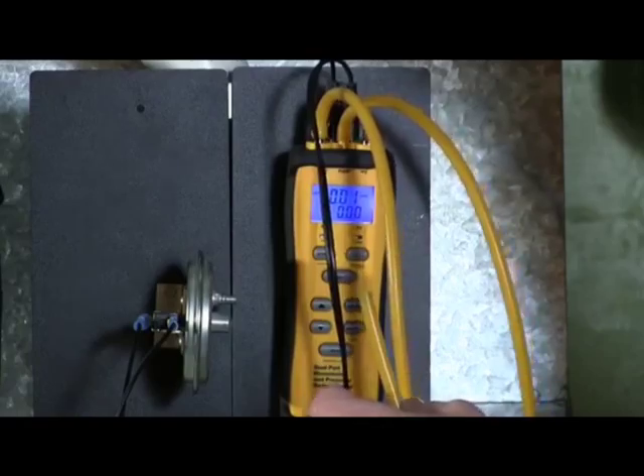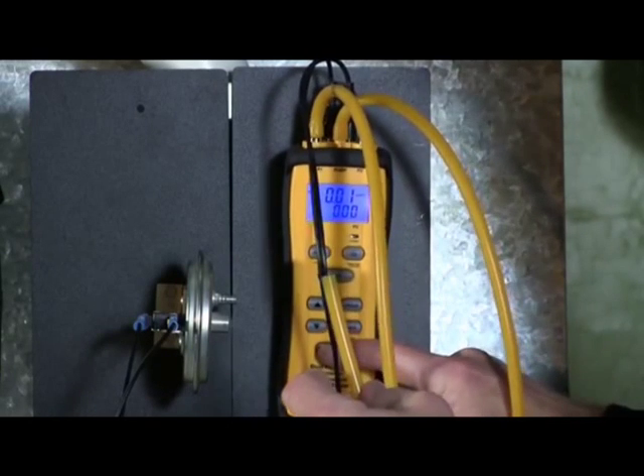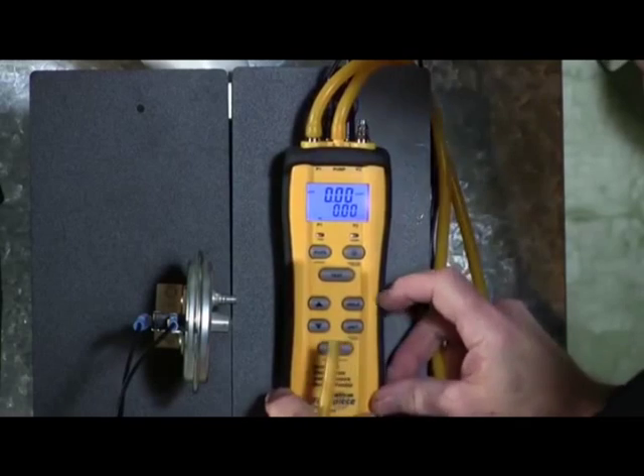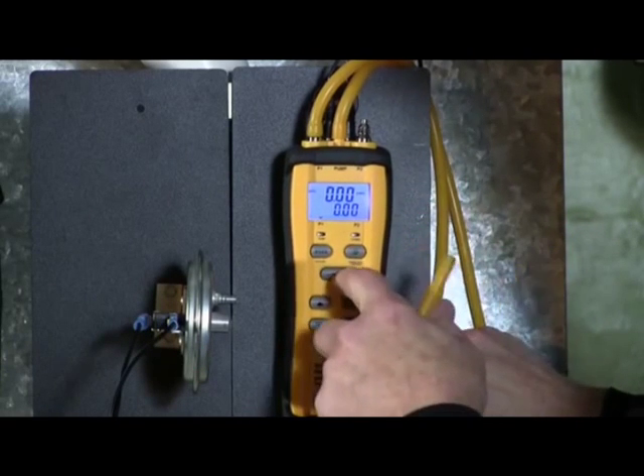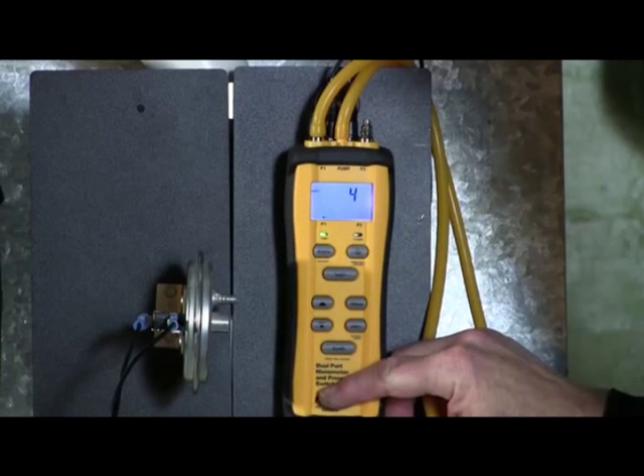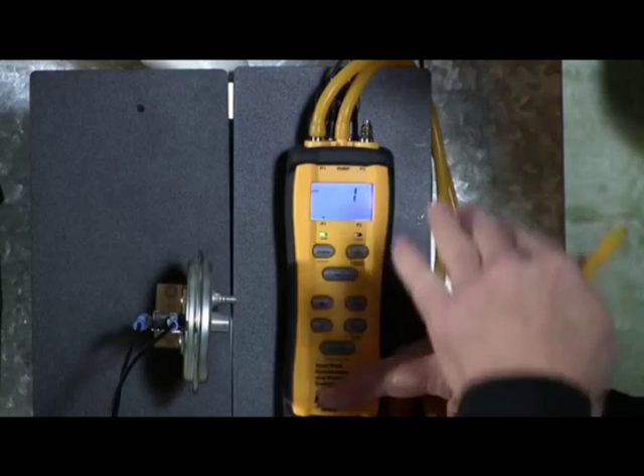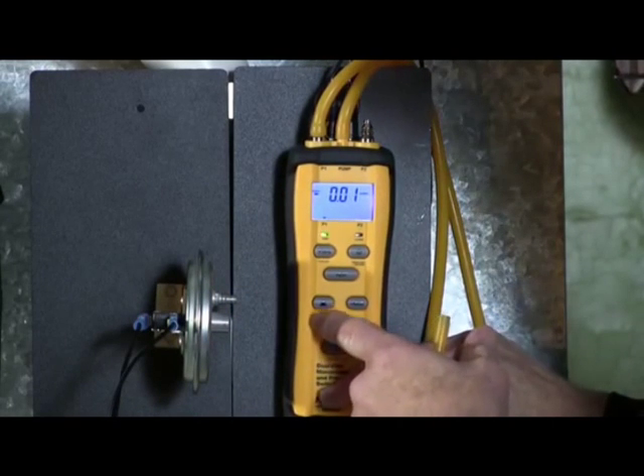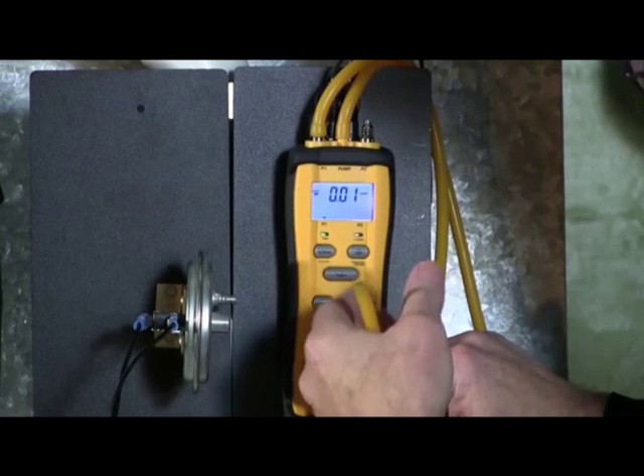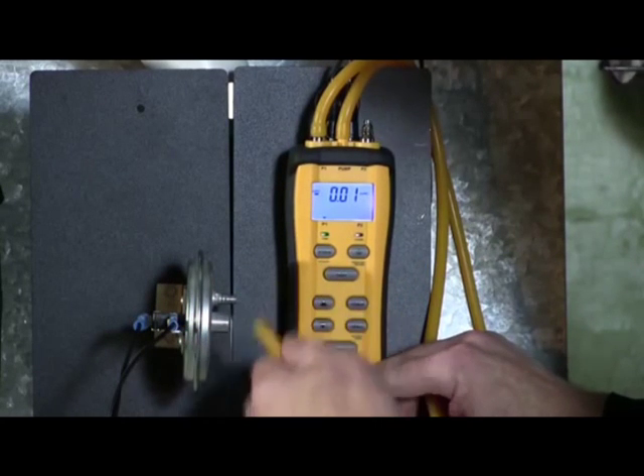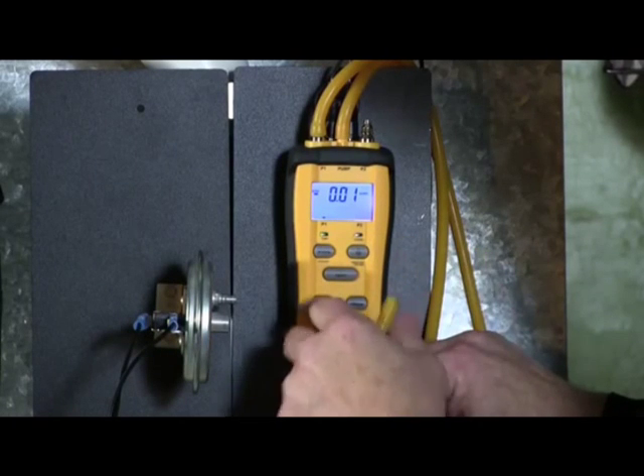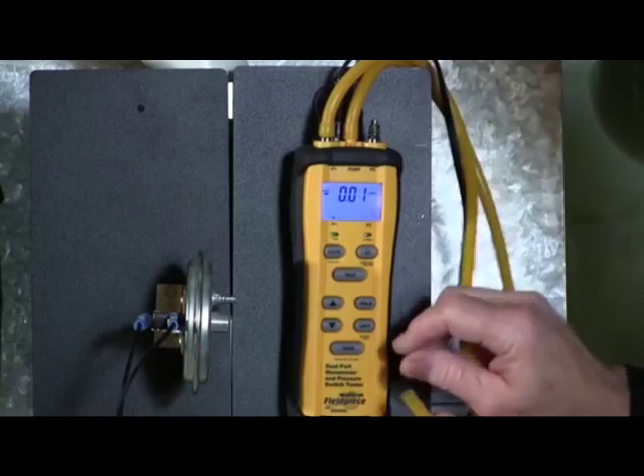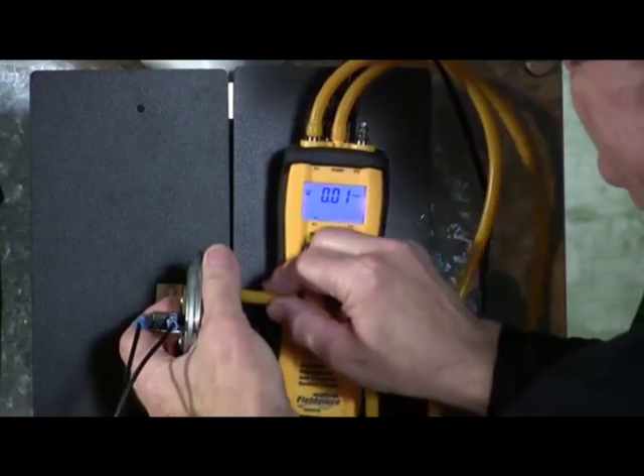When we hook this up, we could use the arrows to increase or decrease the speed depending on where we are on the switch. If we hook it up and the red LED is closed, that means our pressure is a little bit higher. I'm going to plug this in. We're going to go up and take this up in increments, increasing our pump speed. We see it was 1.67. Now we're going to take it down and see where it opened. It was 1.64 or 1.63 basically.